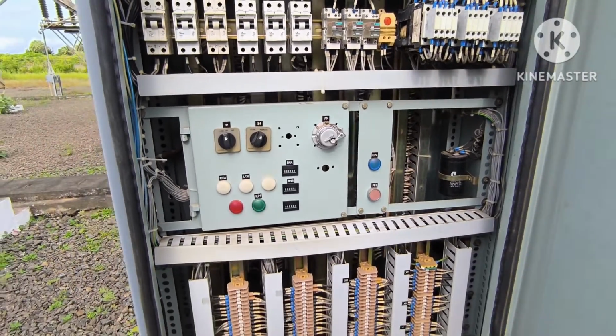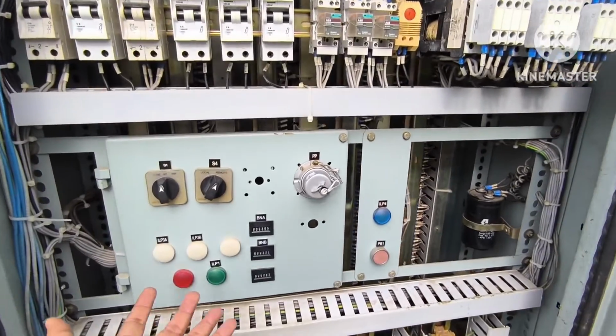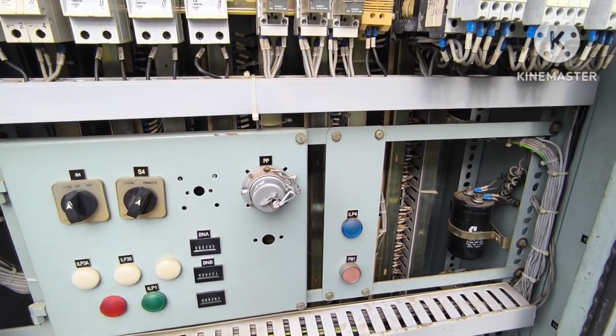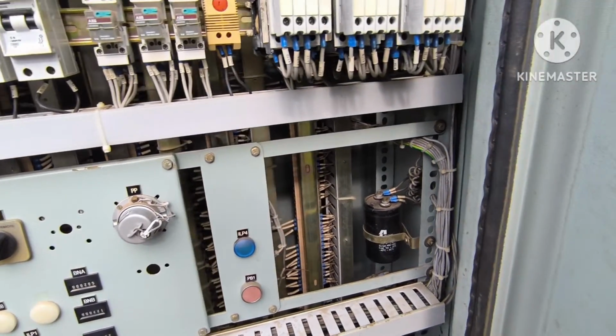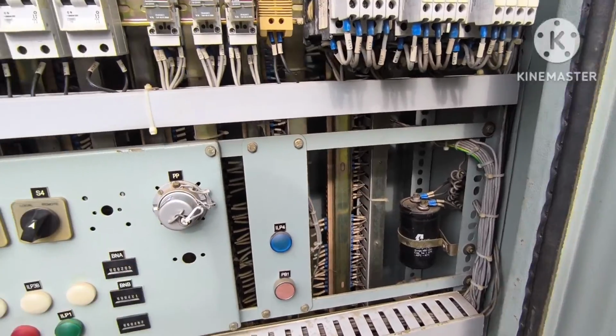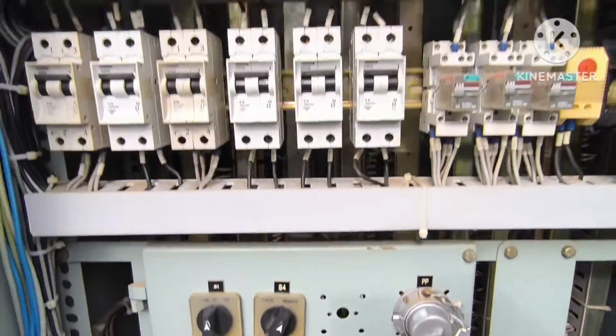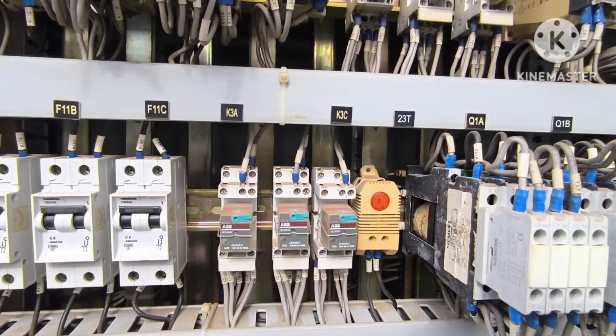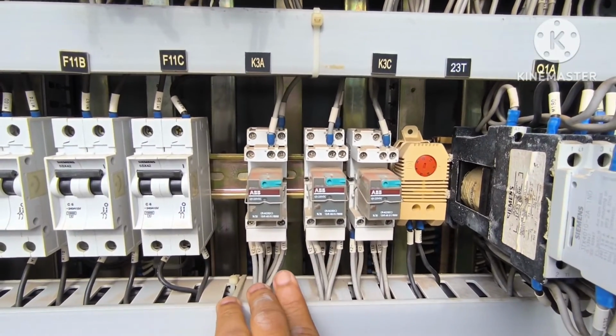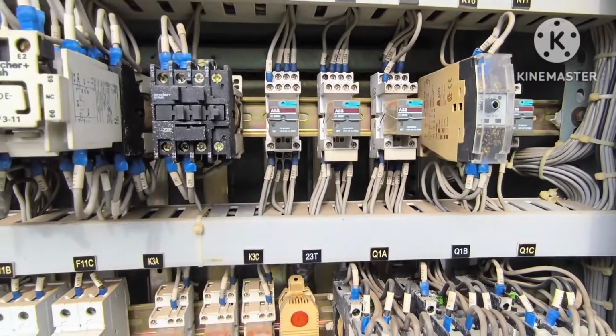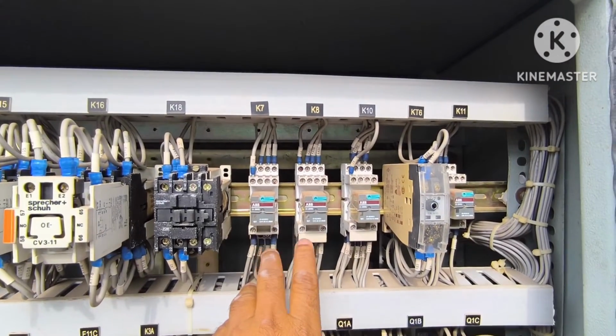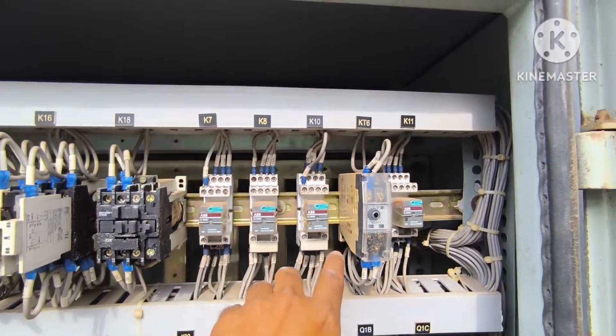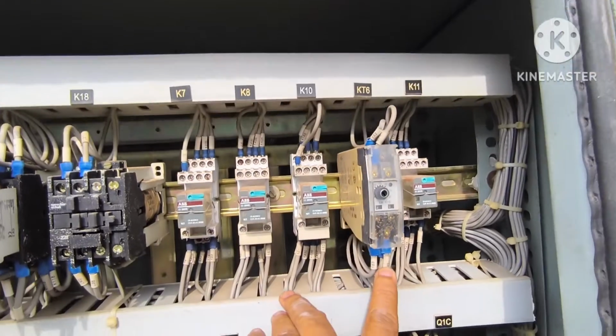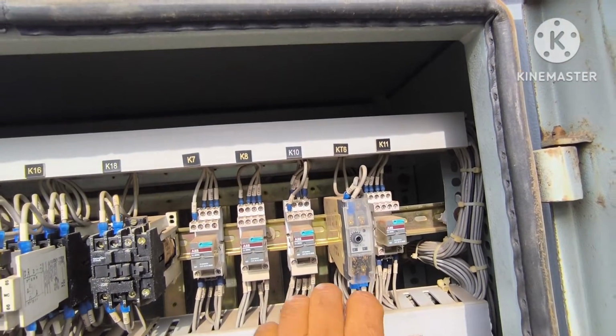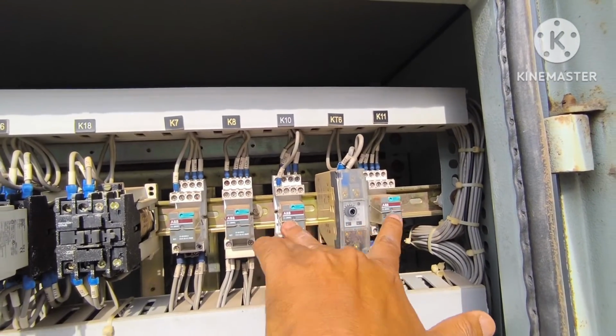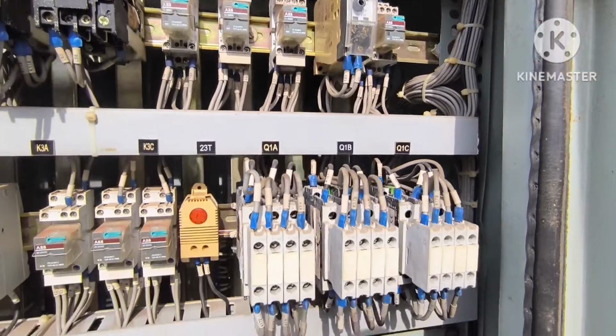So these are the components inside the marshalling box. These 3 white color indications are the spring charge indication. This is breaker on, breaker off, and this is the breaker operation counter. These 3 are K3 actually. This is the anti-pumping relay. K7, K8 are the pole discrepancy relays, for which there is a timer of 3 seconds. And K10 and K11 are the gas supervision relays.